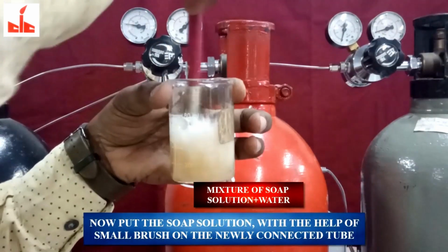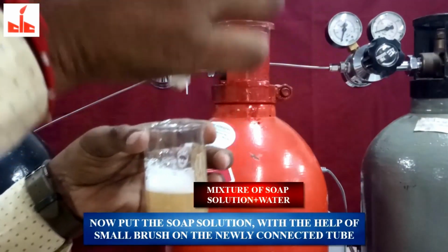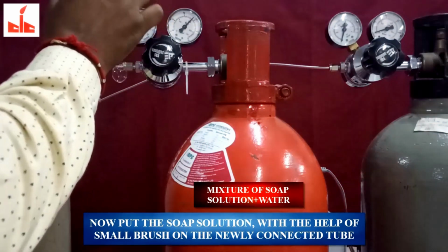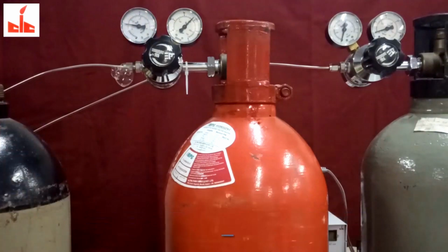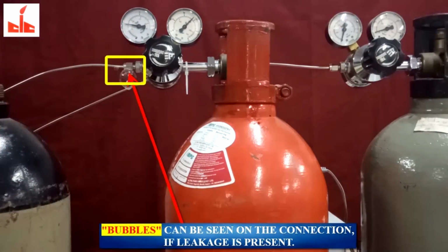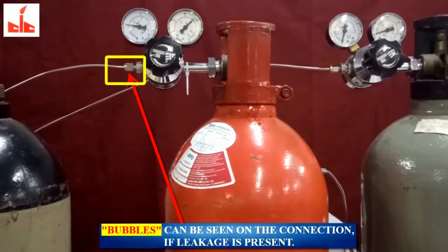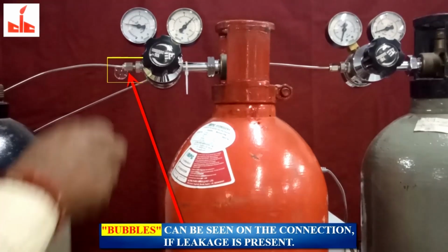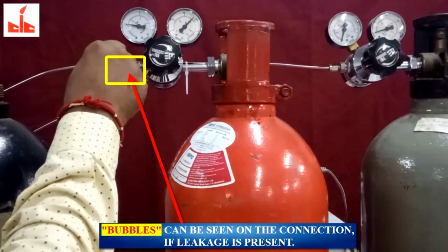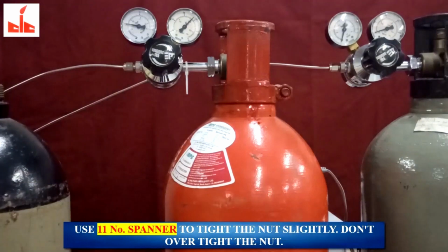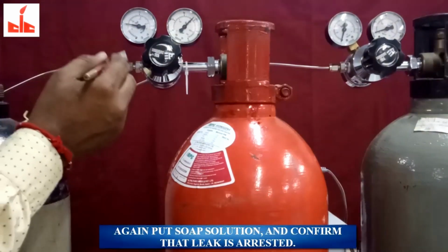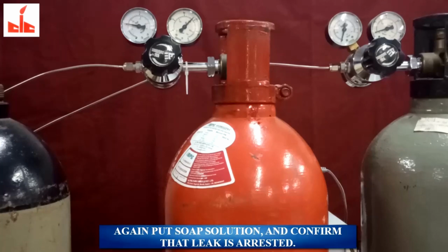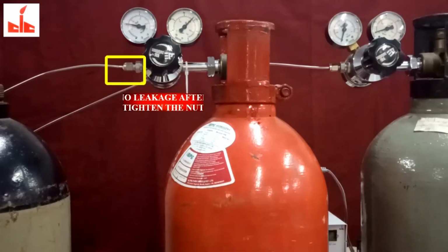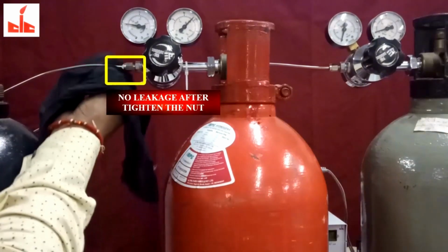Now put the soap solution, with the help of small brush, on the newly connected tube. Bubbles can be seen on the connection if leakage is present. Use 11 number spanner to tighten the nut slightly. Don't over-tight the nut. Again put soap solution, and confirm that leak is arrested. No leakage after tighten the nut.